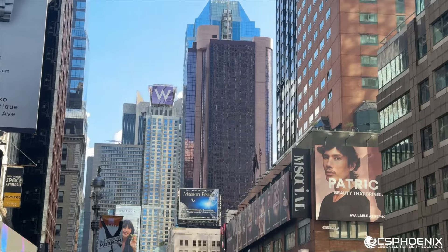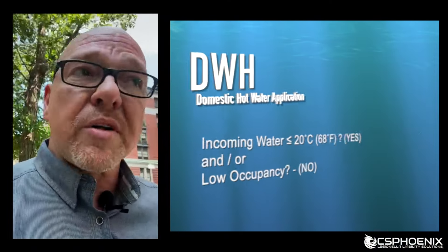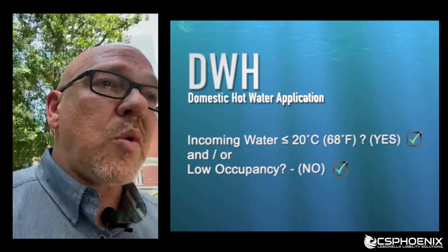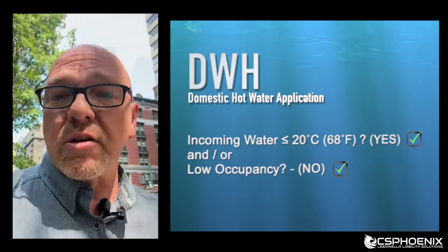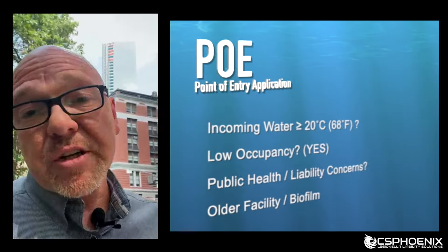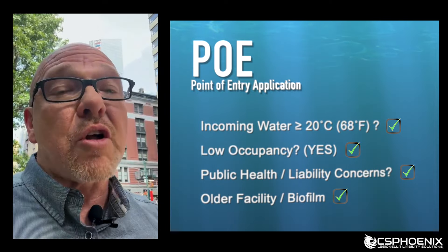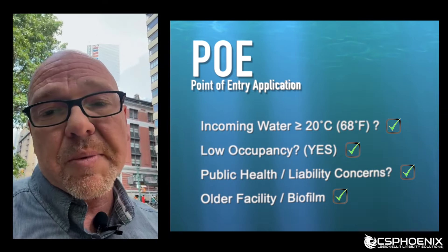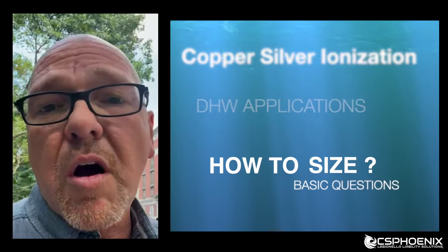This can be determined by the type of building. If it's fully occupied, you might just want to focus on the hot water side. If you are a facility with a low occupancy rate and there might be a lot of stagnation in the building, then you might want to focus on all of the water coming into the building. For now, let's focus on hot water.